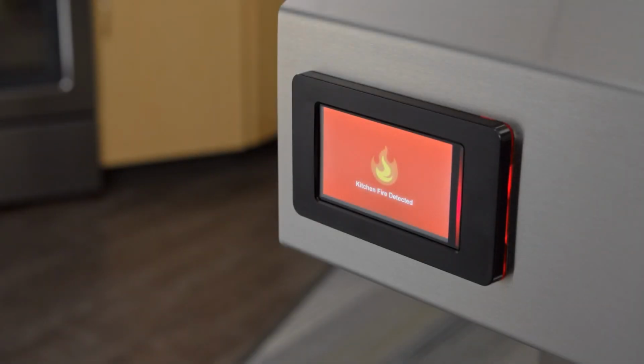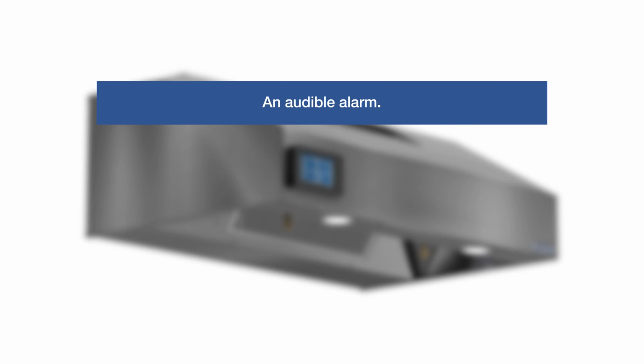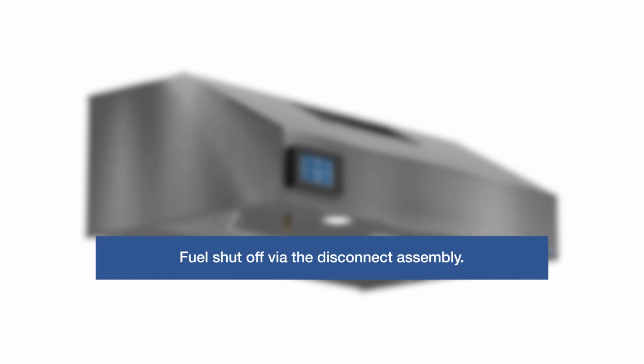A fire alarm sequence will only occur after the detection of extreme high temperatures exceeding 216 degrees Fahrenheit, or if the optional manual pull station is pulled. The fire sequence causes an audible alarm, fire system wet chemical discharge, and fuel shutoff via the disconnect assembly. For resetting the fire system and fire chemical cleanup, please consult the IOM or call factory technical support for more details.